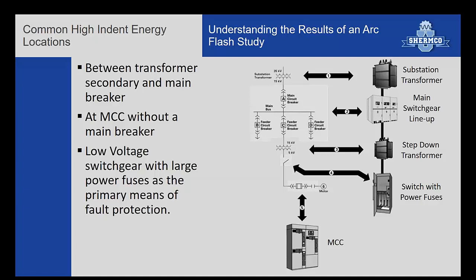Okay, just want to talk about some of the common areas that we find high incident energy when you get your study. Typically between the transformer and the secondary, so where power is coming in, this area, there's no protection between the secondary and the main breaker. So we typically see that to be a very high incident energy. And then same thing when you have an MCC without a main. We see lots of MCCs with very high incident energy. And then especially in commercial buildings, there are some industrial that have low voltage switches feeding the lineup of other switches. Large low voltage switches used as a main, everything downstream of them typically have a very high incident energy.